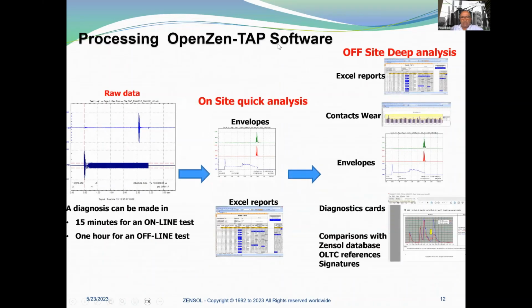And here we have a software, and typically we have the raw data. Here you can see an AC current with a vibration that we record. A diagnosis can be made in 15 minutes for an online test and 1 hour for an offline test. So here, this is the on-site quick analysis. Thanks to the envelope, we are able to see quickly if the tap changer is working properly or not. We have some Excel reports, and in dark blue here, we see there is something you have to be careful with.